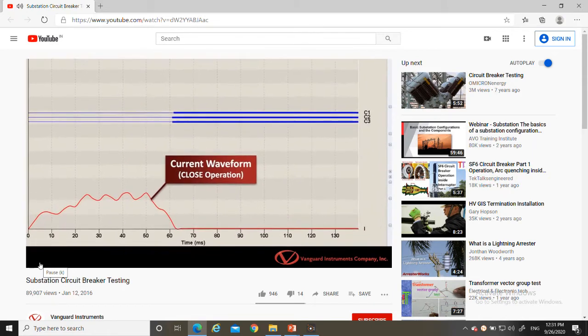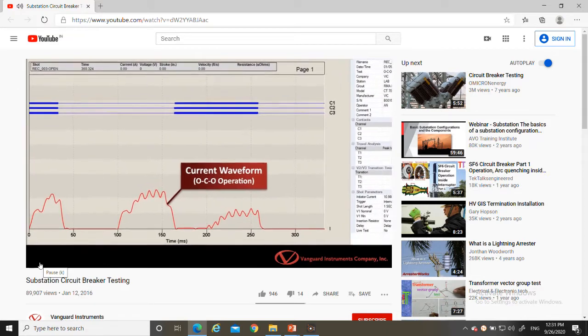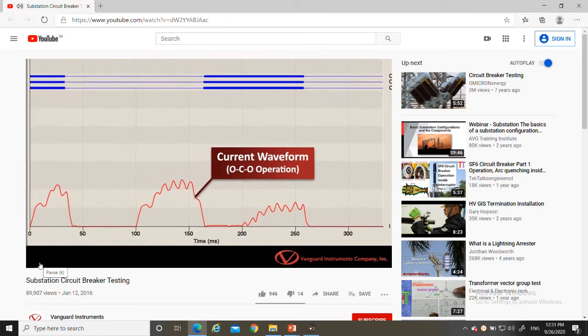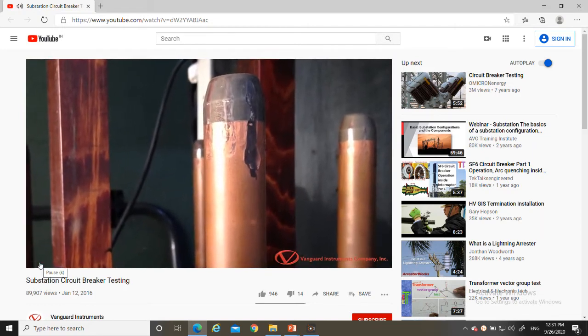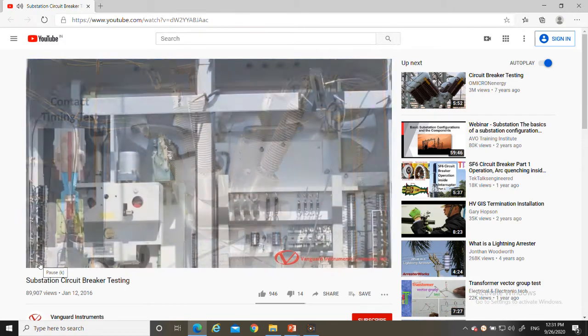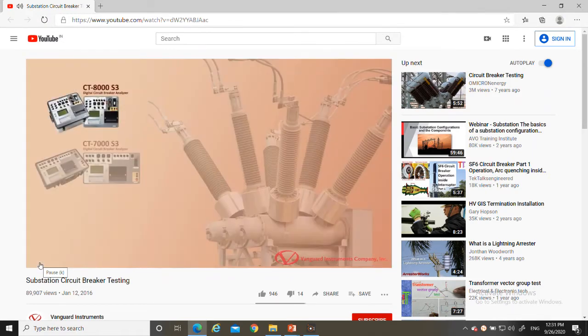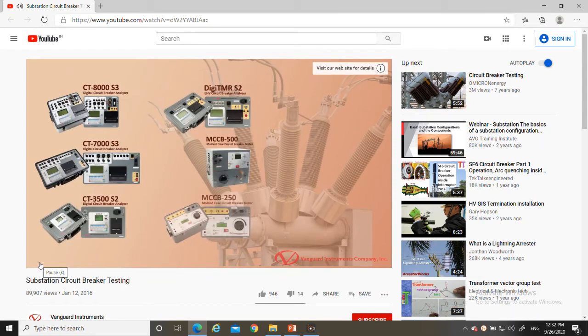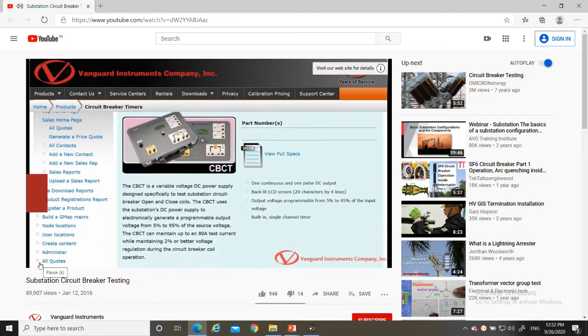The operating coil's current waveform provides insight into the mechanical and electrical condition of the operating coils — any significant changes from the benchmark test signature should be further investigated. Contact wear is another important factor affecting breaker performance; a dynamic resistance test can analyze the breaker's contact condition during operation. To maintain optimum breaker performance, these various tests should be routinely performed. Vanguard Instruments offers a wide range of circuit breaker analyzers to make routine testing safe, convenient, and cost effective.